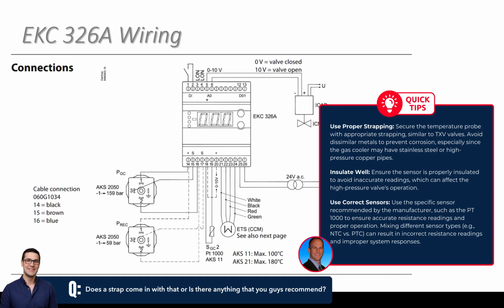well. Yeah, we've had those calls for sure where a guy doesn't understand why the valve's either all over the place or it's not opening or closing when it should be, the high pressure valve. And we get around to asking some questions, and it's usually not the first place we go to because we assume it's been installed properly. But there's definitely been times where we've asked that question and come to find out they didn't insulate it at all. And I've also seen, Chris, where they bring like an Emerson or a Copeland sensor up to it.